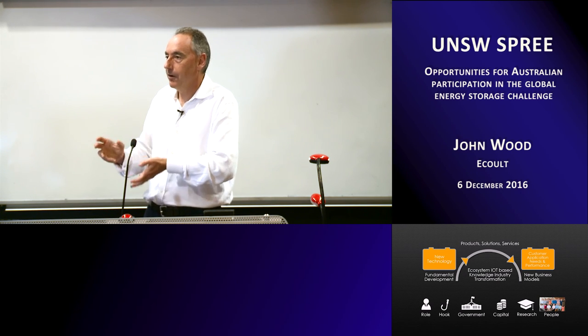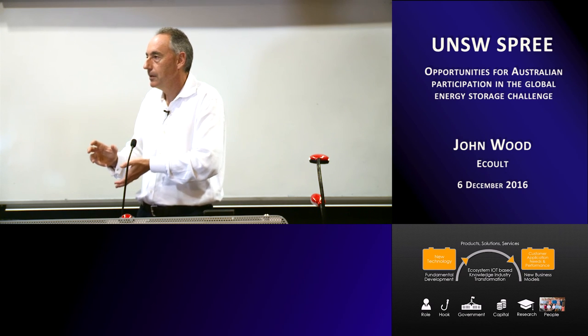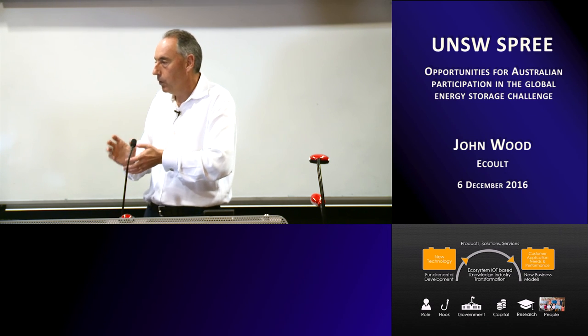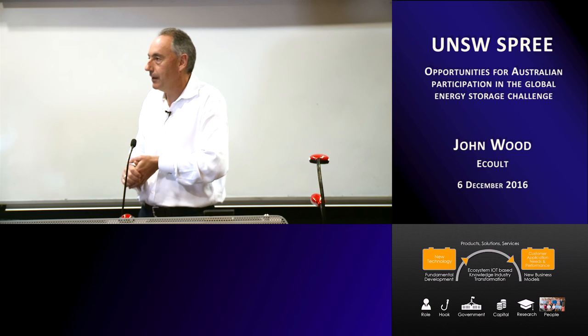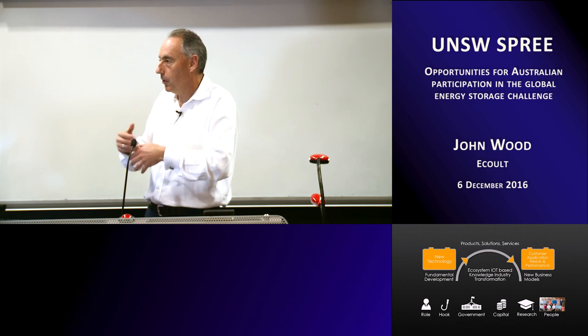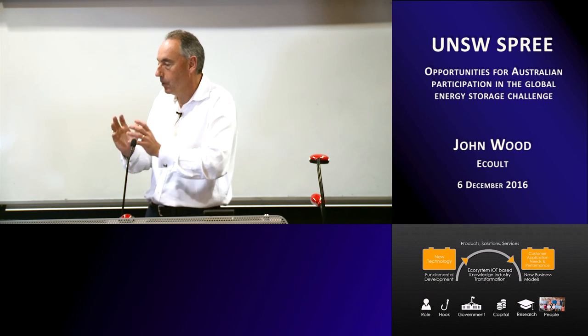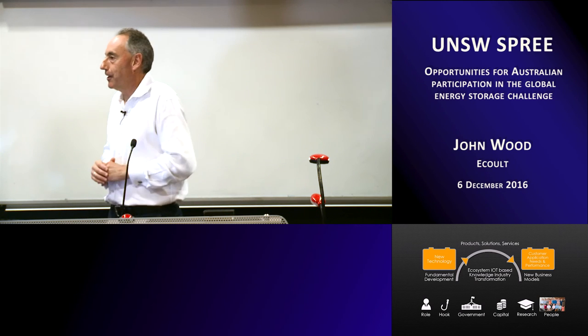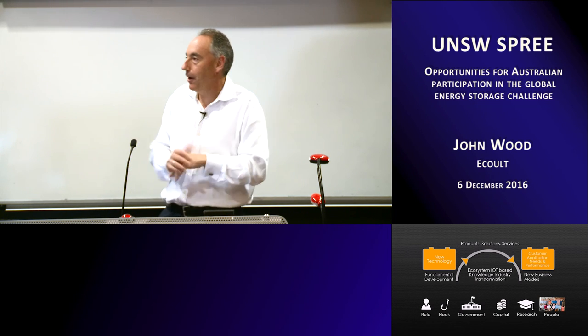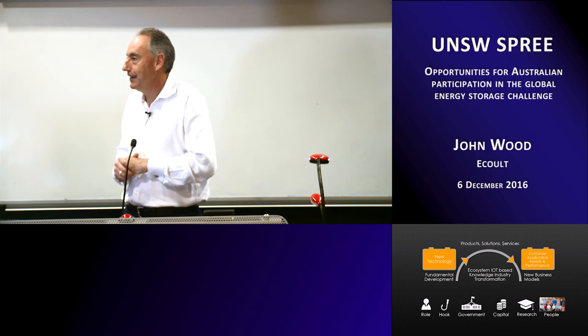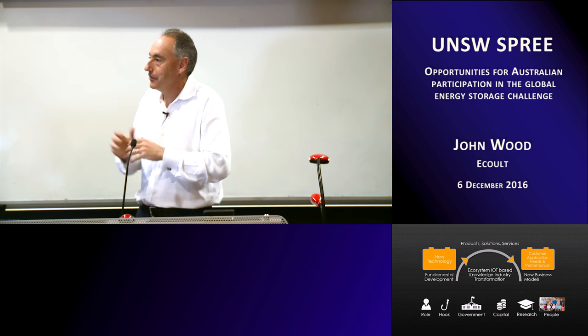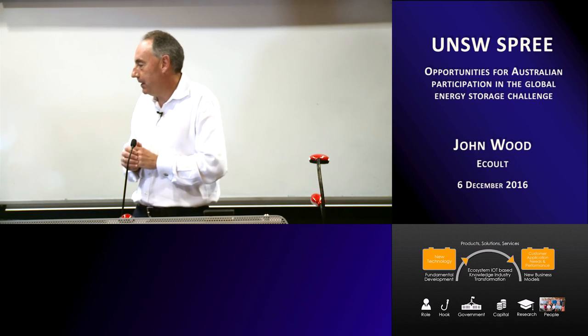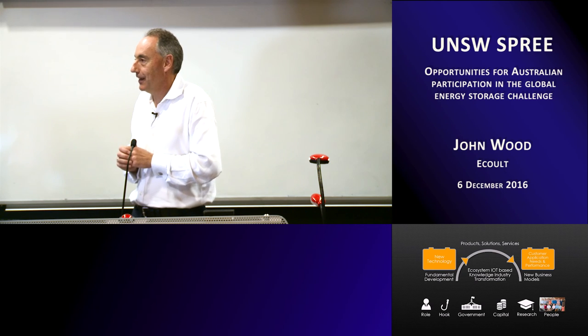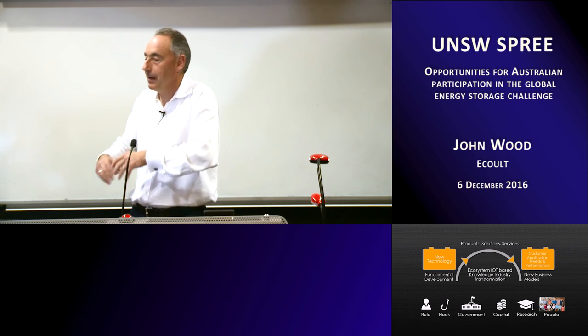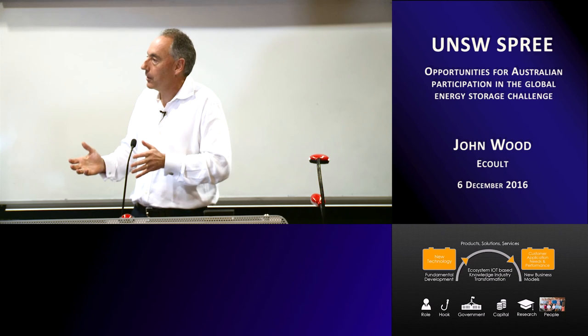So if you take the battery and make it hot, the positive grid will corrode faster. It will generate, split more water for the time that it's hot. But if it's really hot, say 45 degrees for 4 hours, then that might be equivalent to 20 hours at 30 degrees. But it's all incremental — that's what I call soft edges.